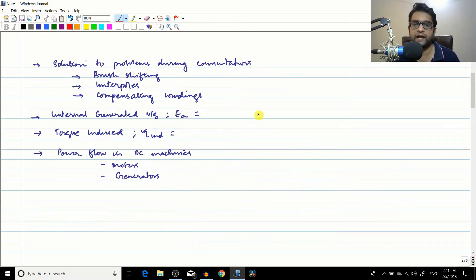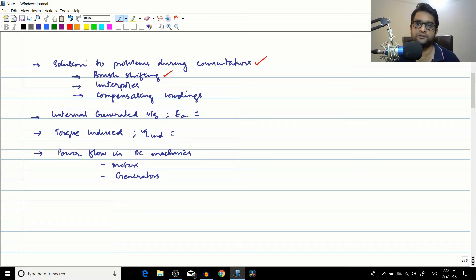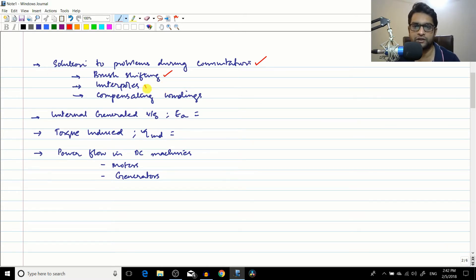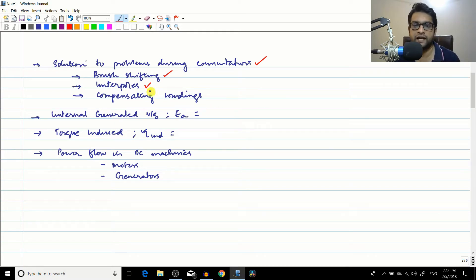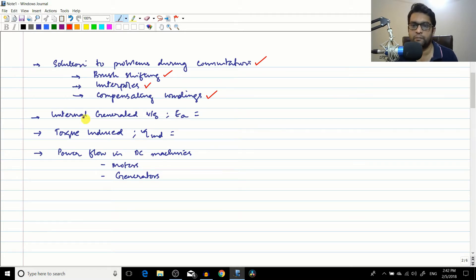We then had a session on solutions to these problems — how to reduce armature reaction and the L·dI/dt voltage. One solution was brush shifting, manually moving the brushes to the new magnetic neutral plane, but that is not ideal. A better solution is interpoles, which compensate for L·dI/dt voltages in the brush axis. Interpoles do not reduce flux weakening, so compensating windings are added. A combination of interpoles and compensating windings makes commutation much more efficient.